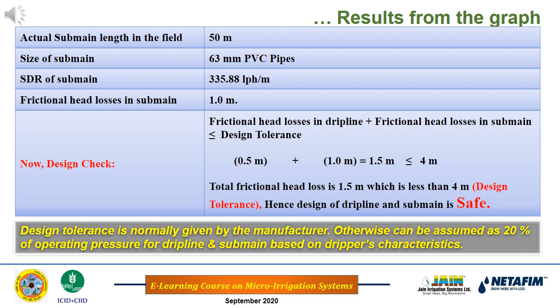Result from the graph. Actual submain length in the field is 50 meter, size of submain is 63 millimeter, SDR of submain is 335.88 liter per hour per meter. Frictional head losses in submain comes to 1 meter.